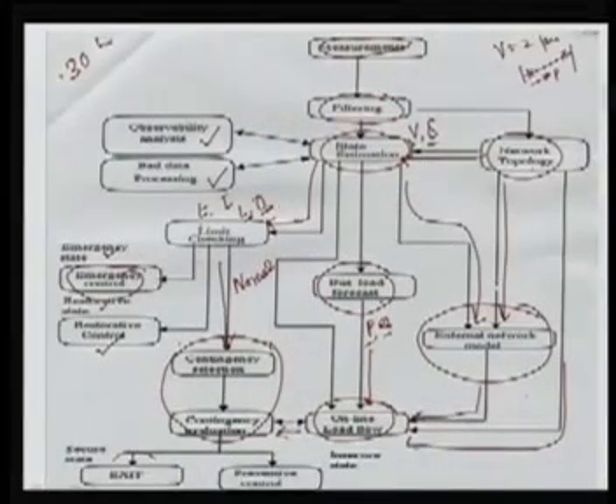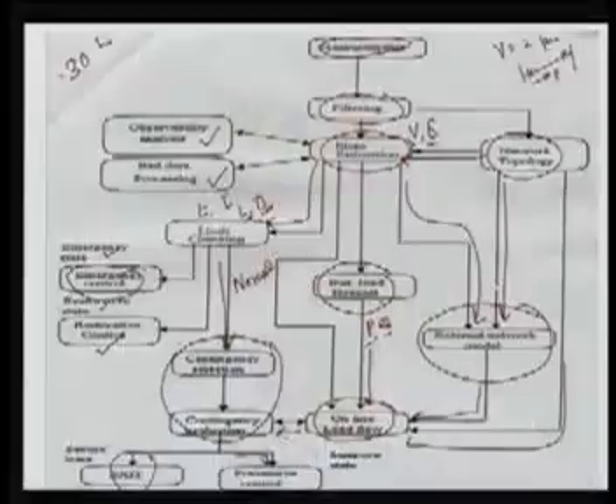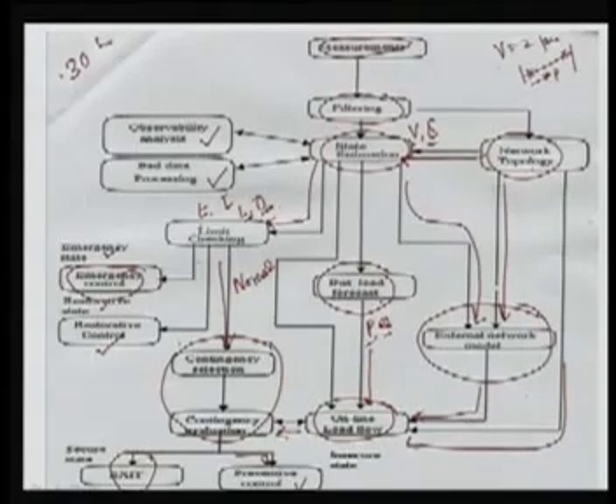So if it is in a secure state, then you can go for optimal power flow and so on. If your system is in an insecure state, then you have to go for some preventive action, and at the same time you can apply security constraints, optimal power dispatch, because here you are going to control something. You are going to change the settings of some of the outputs of the generators, maybe the elements of your power system. At the same time, it is possible that we can set our generators in such a fashion that we can achieve minimum cost operation, and then it is called security constrained optimal power dispatch.